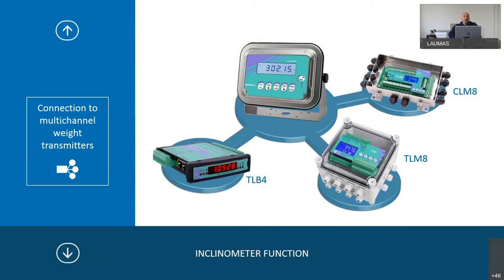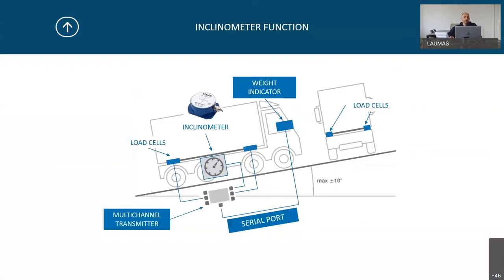There is the possibility to connect the LAUMAS indicator to a multi-channel transmitter, and you can command and make calibration directly from the indicator. Here we have an on-board weighing example where you can see an inclinometer sensor to determine the position of the means of transport. We have a multi-channel transmitter connected to the load cell and the inclinometer, and via serial port the multi-channel transmitter is connected to the weight indicator.